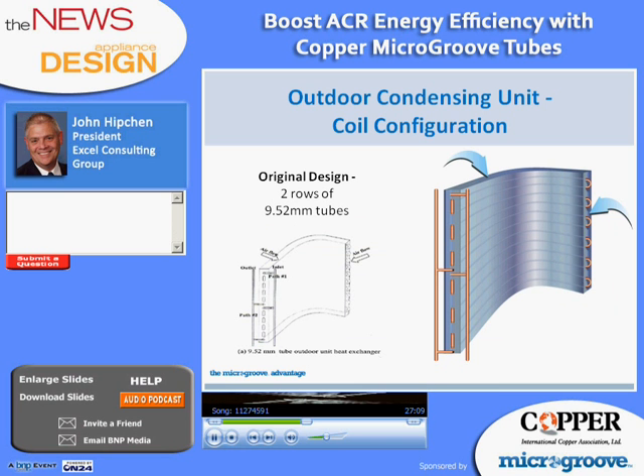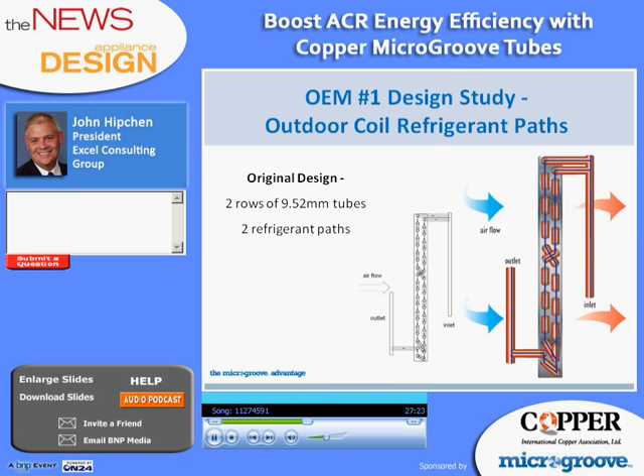The original design moves air horizontally through a curved coil made of 2 rows of 9.52 millimeter copper tubes. The illustration here is just showing us the concept. This is the circuit diagram showing the paths that the refrigerant travels through this coil. Notice that the refrigerant flows the opposite direction of the air. We've got the inlet on the right, the outlet on the left, but air moving left to right.